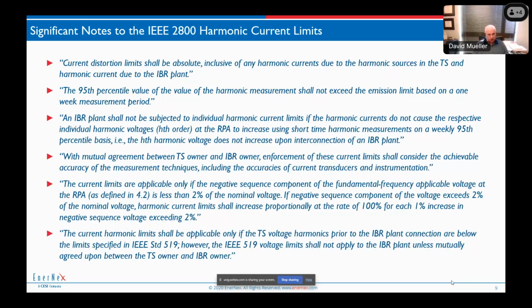There are, however, a lot of notes in the standards, and some of the notes I like and some of the notes I don't like. The first note is one of the ones that I don't like. The current distortion limits shall be absolute, inclusive of any harmonic current due to the harmonic sources in the transmission system and also the harmonic current due to the IBR plant. The reason I don't like this is I ask myself, why do I have to be responsible for currents coming from harmonic sources that I don't control? But that's what it says. So it doesn't matter whether I like it or not. That's what's in the standard.